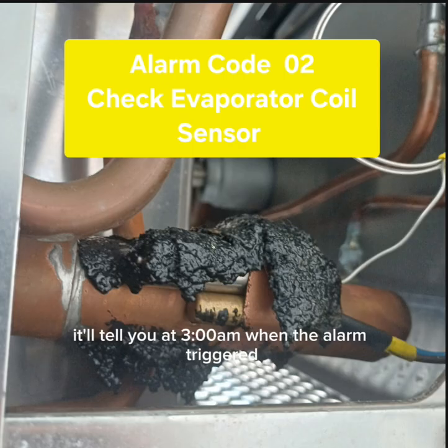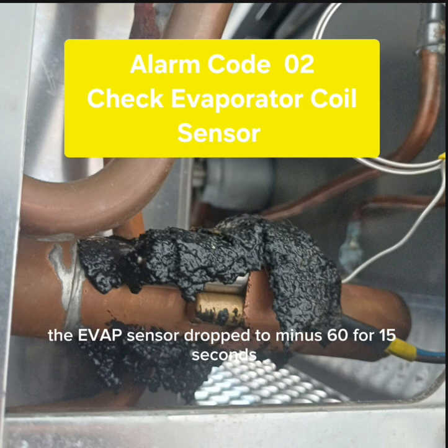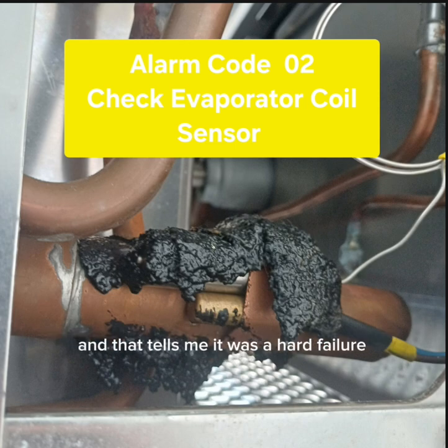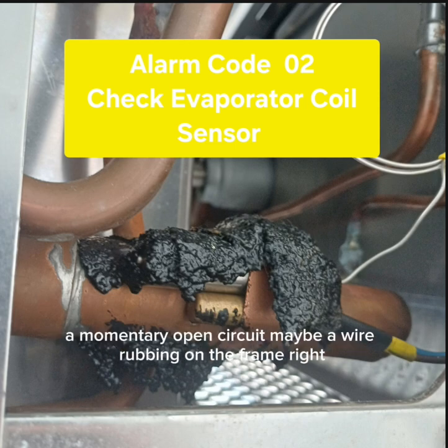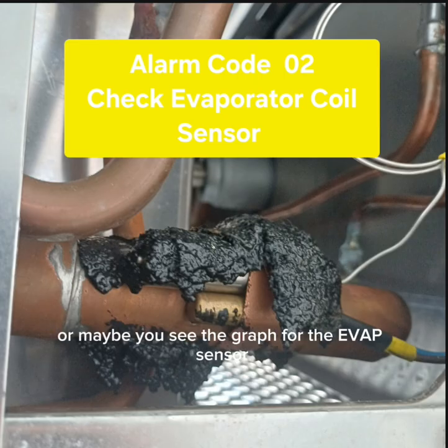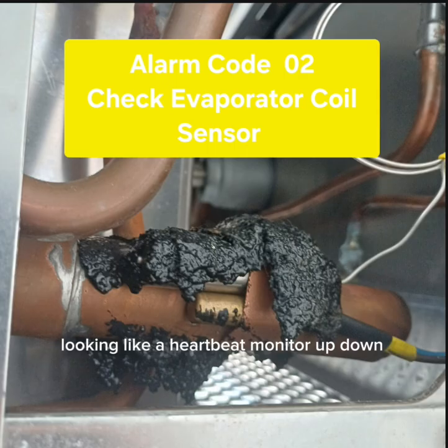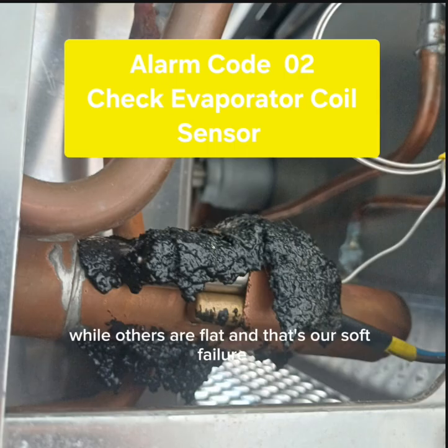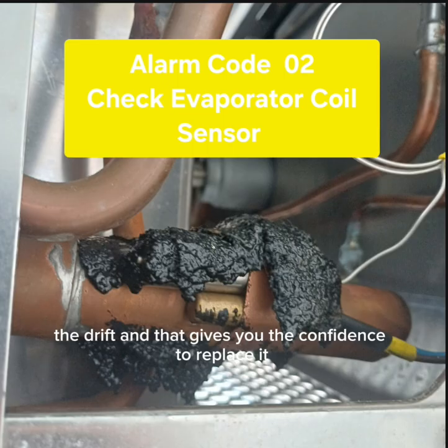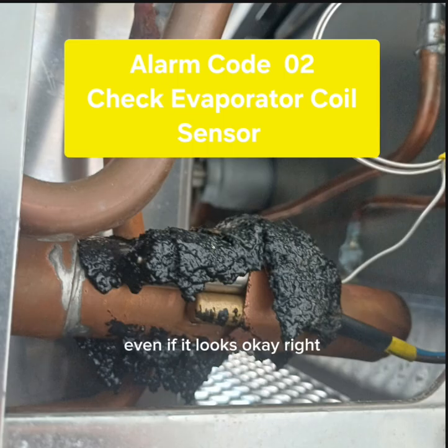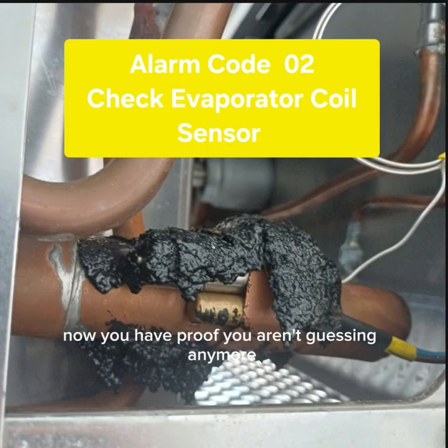It'll tell you at 3 a.m. when the alarm triggered, the evap sensor dropped to -60 for 15 seconds. And that tells me it was a hard failure, a momentary open circuit, maybe a wire rubbing on the frame. Right. Or maybe you see the graph for the evap sensor looking like a heartbeat monitor, up, down, while others are flat. And that's our soft failure, the drift. And that gives you the confidence to replace it, even if it looks okay right now. You have proof. You aren't guessing anymore.